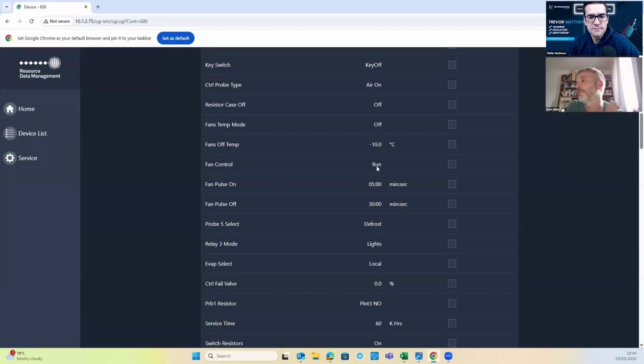With fan control, you can tell the fans to run all the time. You can tell them to run when cooling's on and not run when cooling's off. And if it's not running with cooling off, you can tell it every few minutes, I want to pulse the fans just to blow a bit of air around and check what temperature the room is, right? Because if you switch the fans off, you can't sense the temperature accurately. So it will bring the fans on every so often to do that.